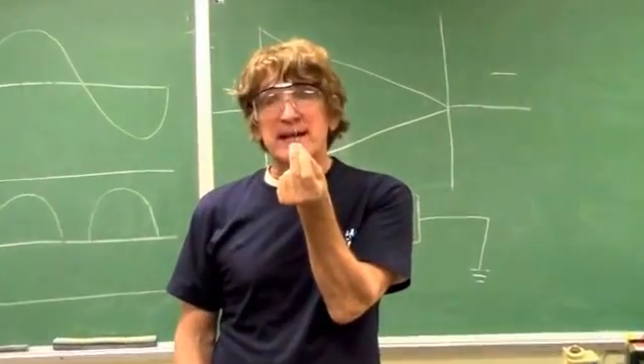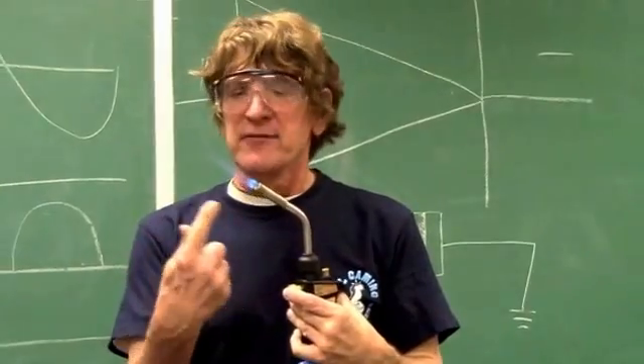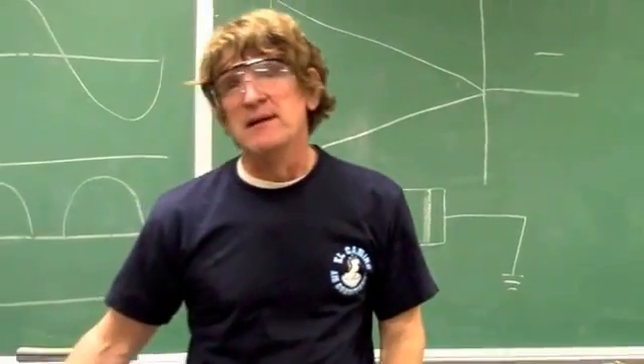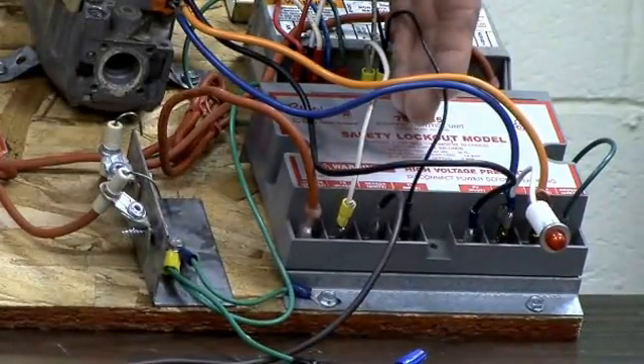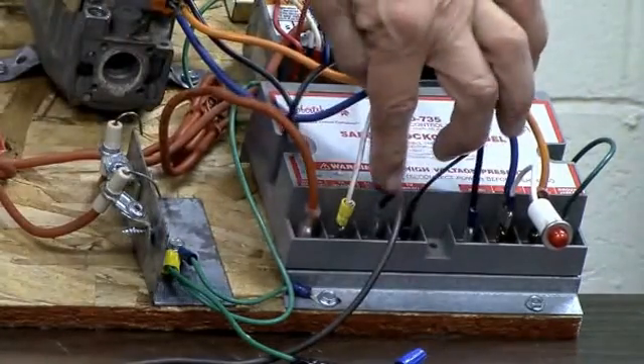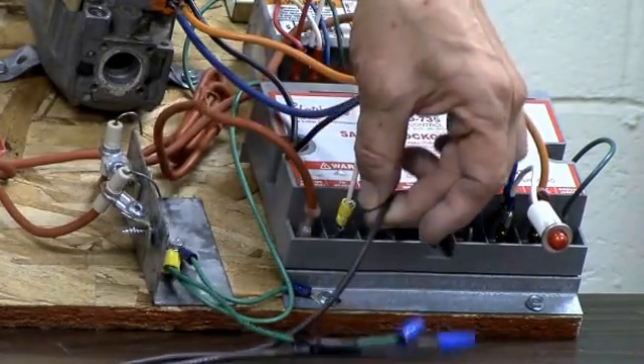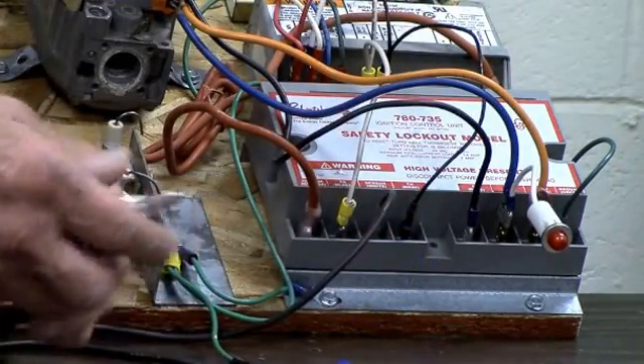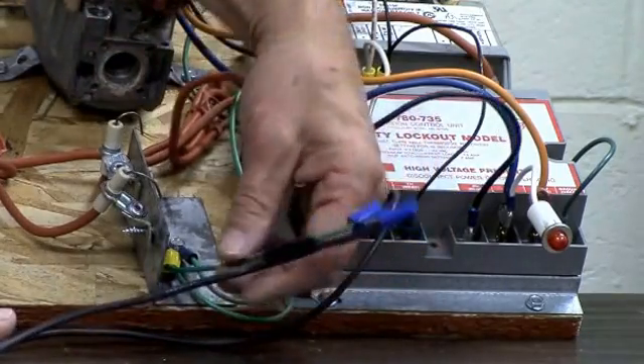This is actually simulating flame rectification through the flame, because as I pass an electrical signal through a flame, it converts it to that pulsating DC signal. This is my ignition module, this is my spark igniter, and my flame sensor is connected here. You'll have to find out on your particular module where your flame sensor input is. I come out from my flame sensor, through my switch, out of the switch, through my diode. The cathode is on the bottom, closest to the green wire, going to ground.